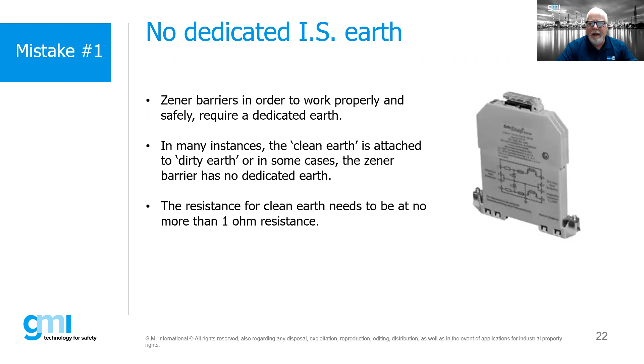And again, the requirement, and this is true no matter where you look, in the NEC or in the IEC or any other international or national standard, is that the resistance on our clean earth needs to be no more than 1 ohm. Sometimes people ask, how big does my cable need to be? The IEC standards do give a minimum size, and that's 4 millimeters. But generally, it might even have to be larger based upon the resistance you need to achieve for the length. So that's probably one of the most common faults we find when we come in and do inspections on IS systems.